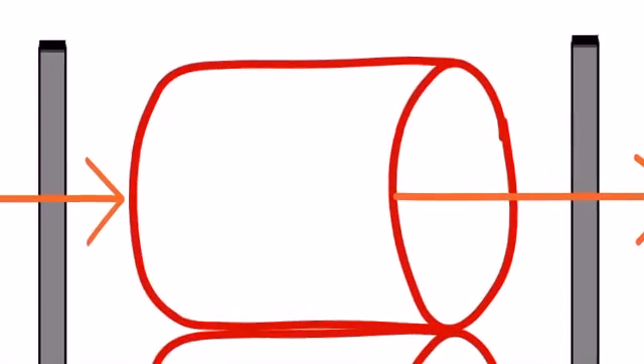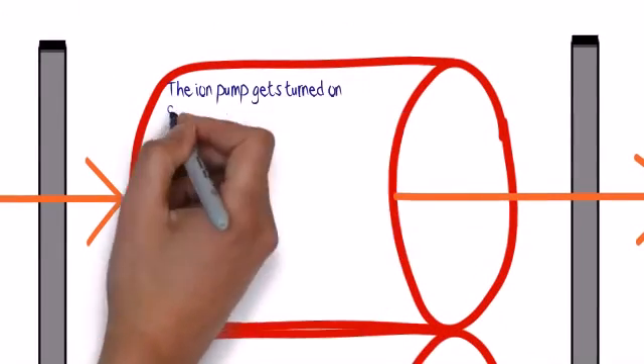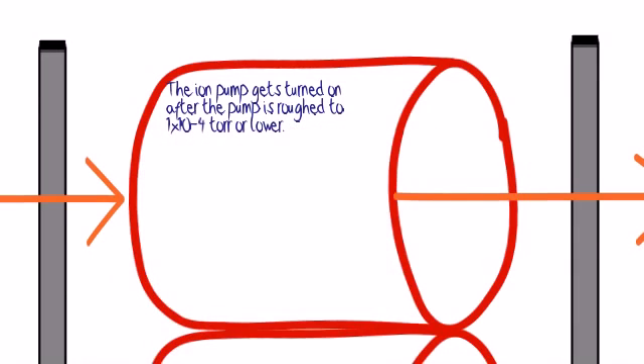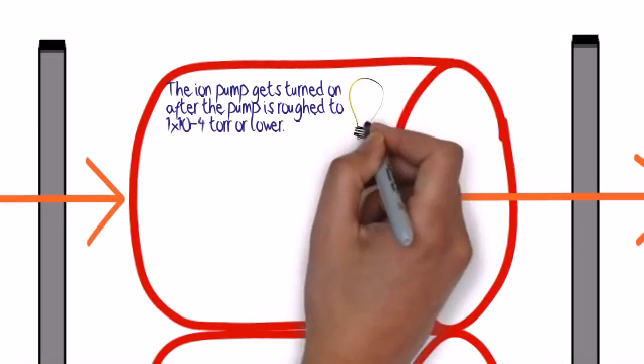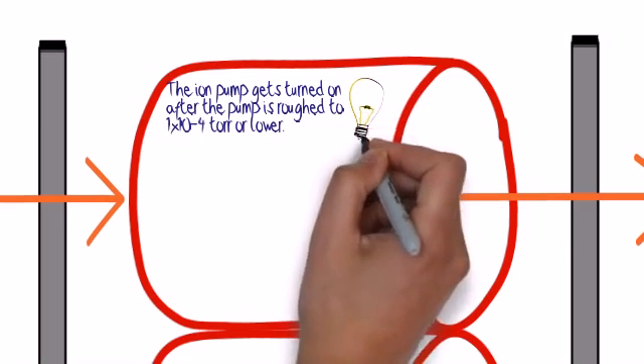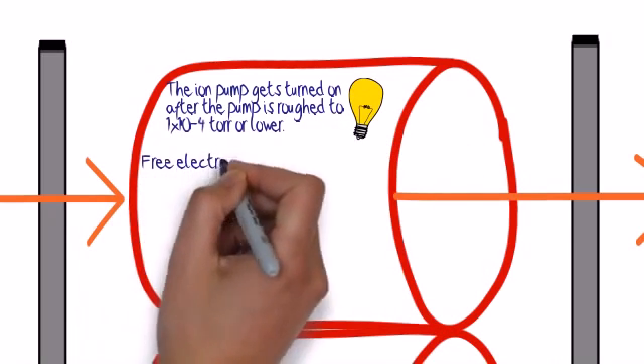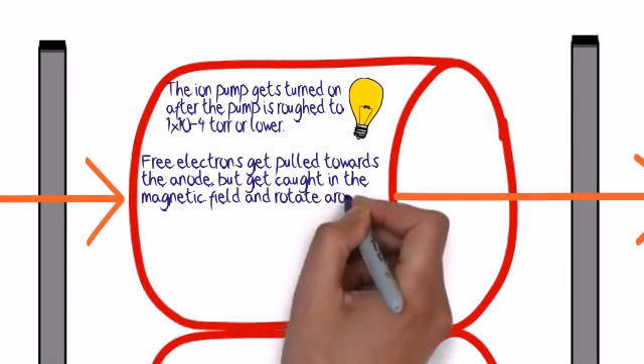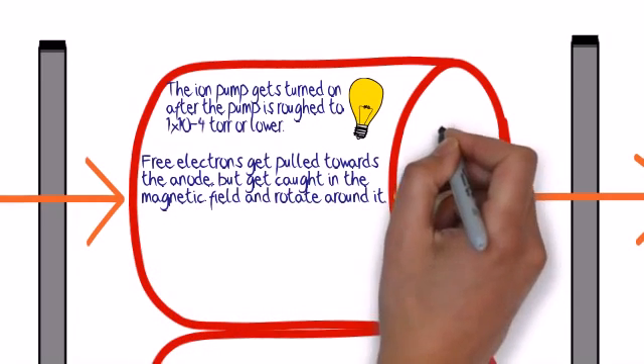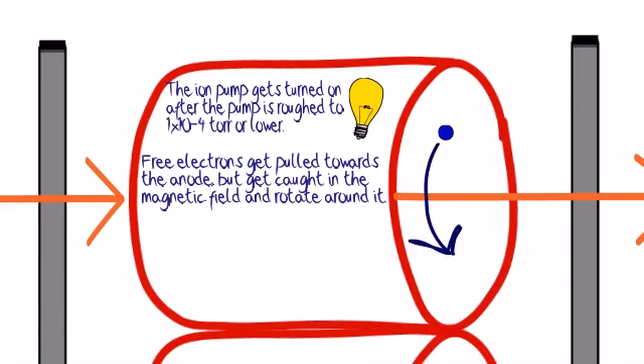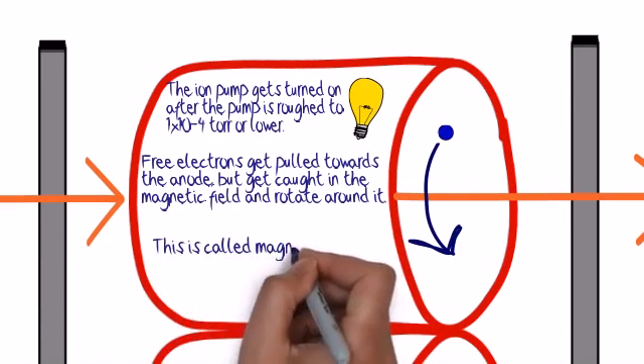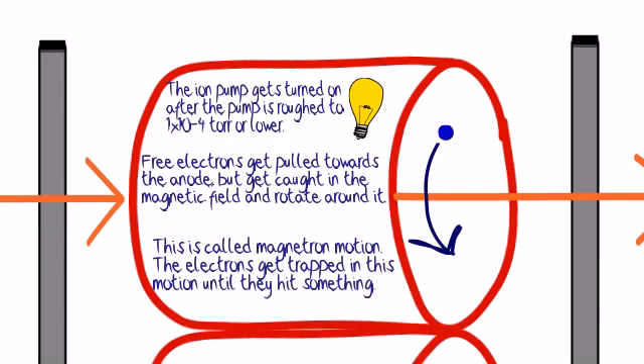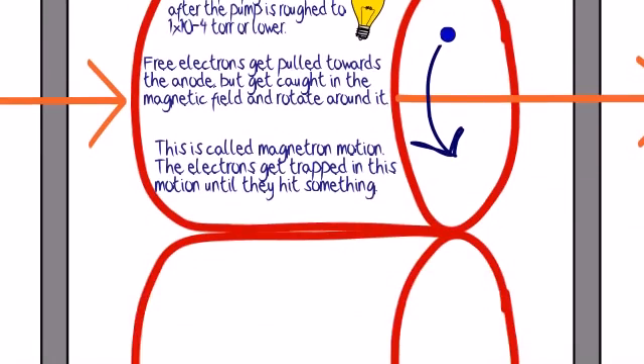Zooming up on that, we're going to actually rough this pump down to 10 to the minus 4 torr or lower if we can, and turn it on. 7,000 volts is what we typically use, but the ion pump will operate between 3 and 7,000. Free electrons are going to get pulled towards that anode assembly, but they're going to get caught in that magnetic field and rotate around it. This is actually called magnetron motion, and the electrons get trapped until they actually hit something like a gas molecule.